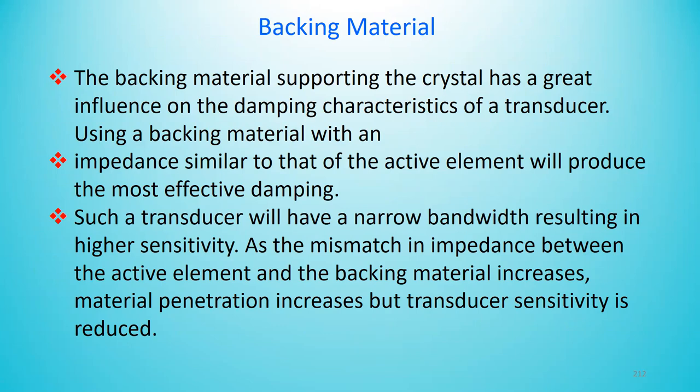As the impedance mismatch between the active element and the backing material increases, the material penetration increases, but transducer sensitivity is reduced. Broad bandwidth, narrow bandwidth, you know.